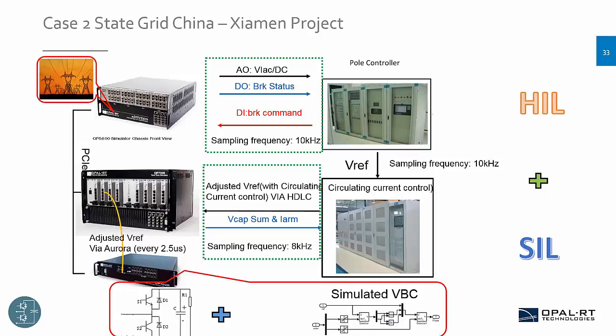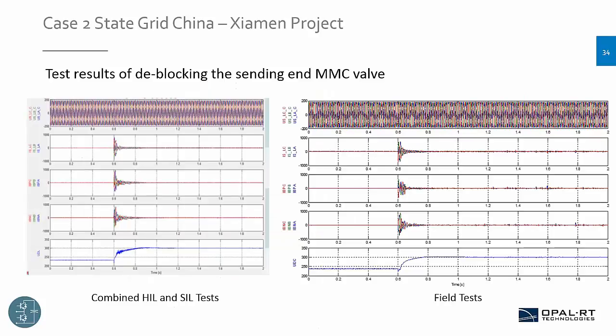So when it comes to the last page of my presentation, the test result of deblocking at the sending end of the MMC valve is compared to the actual field testing result for the same scenario. We can see that the waveforms for both the voltage and current at the AC side and the DC voltage are quite similar. It proves the HIL and the software-in-the-loop platform is quite a feasible solution, particularly when only part of the controller is ready. So this is pretty much all the cases, but I hope you can ask some questions if you want.